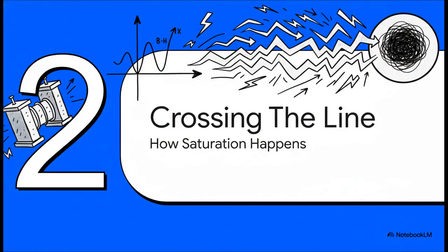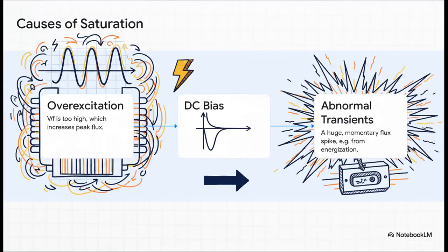Of course, transformers are designed to stay well clear of that knee. So what on earth could possibly push one over the line? How does a perfectly good, well-behaved transformer end up in this dangerous, saturated state? Well, it usually comes down to one of three main culprits. First, you've got overexcitation. That's basically when the voltage is too high for the operating frequency, which just shoves way too much flux into the core.